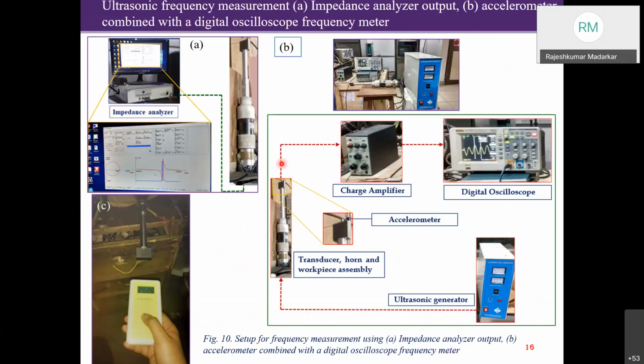And then you want to check whether the developed horn has the frequency that you want. So this is what I have explained earlier. This is a setup for the impedance analyzer. Natural frequency meters are also available. Then an accelerometer combined with an oscilloscope. So you can use any facility which is available with you to check whether your horn has the natural frequency of your generator or not.